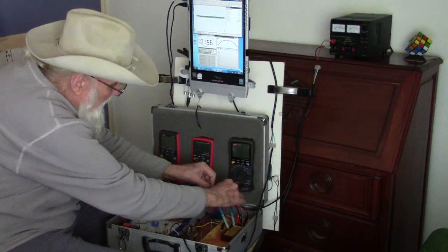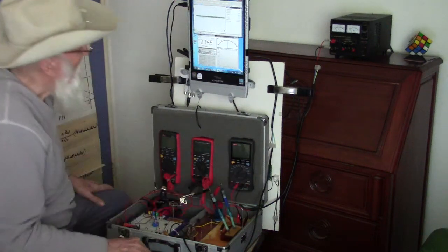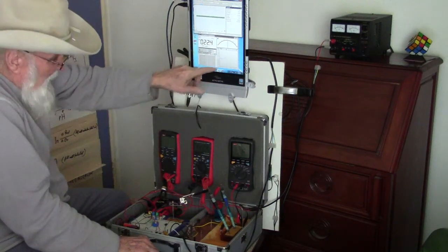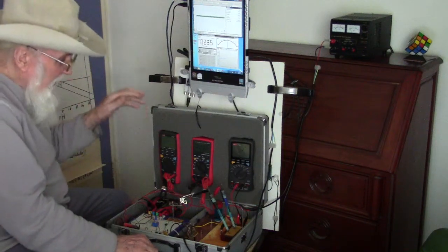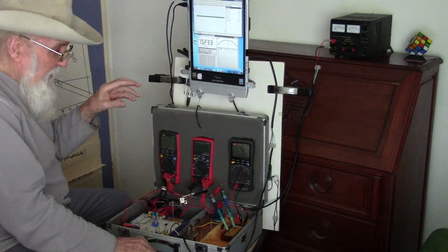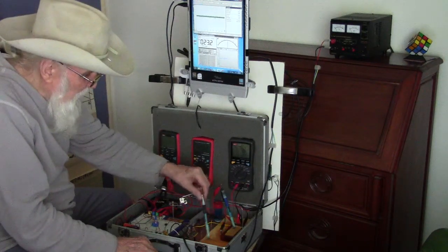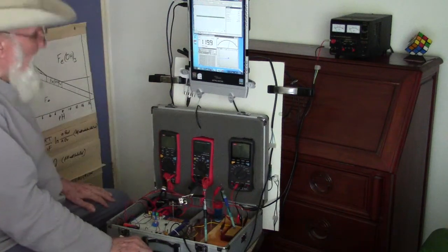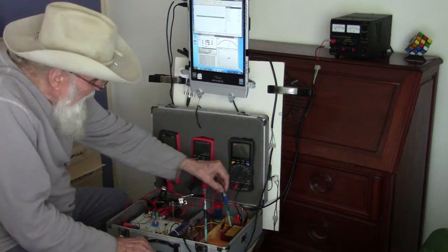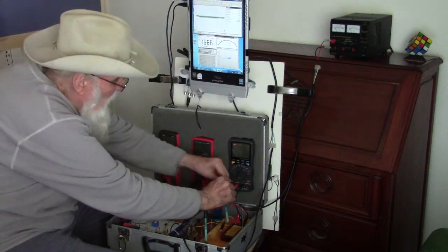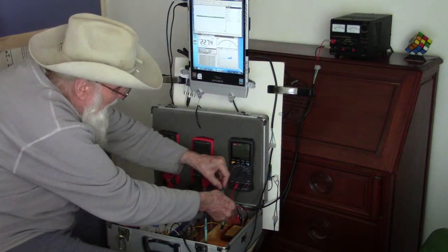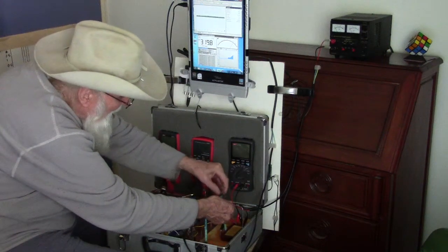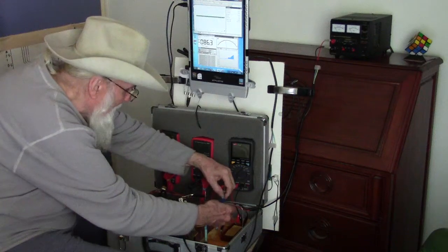Change them over again. You can see all of this has been recorded on here. So we're examining DCVG, which is the voltage between two copper sulfate electrodes. These are not reference electrodes, and they cannot be reference electrodes unless they're set up in a laboratory under closed circuit conditions, and these are not.